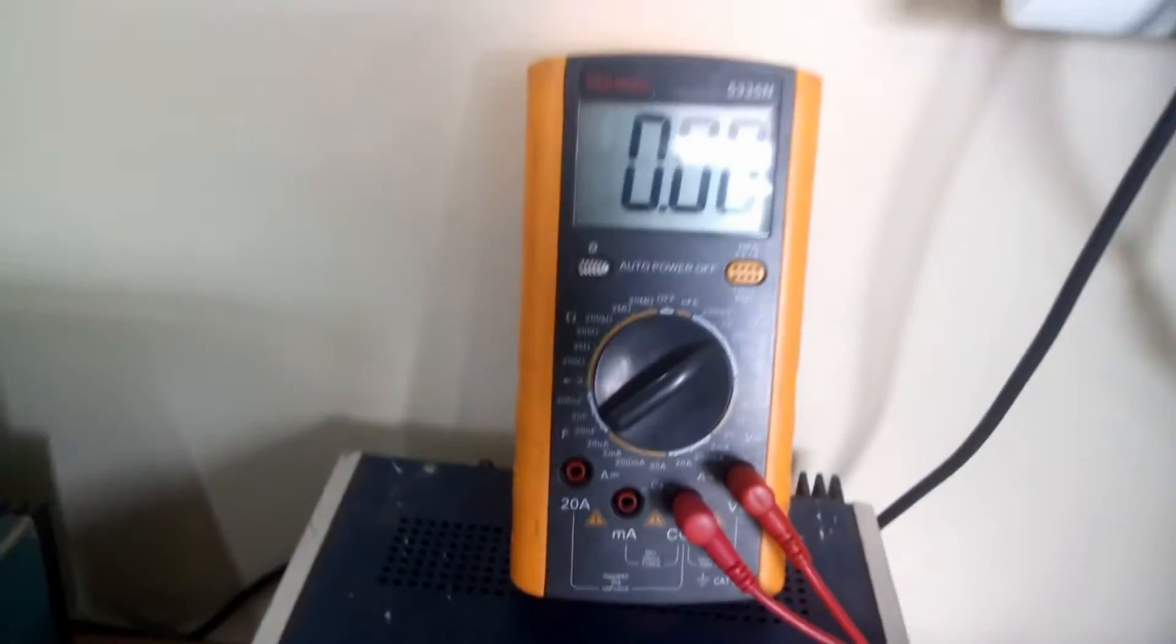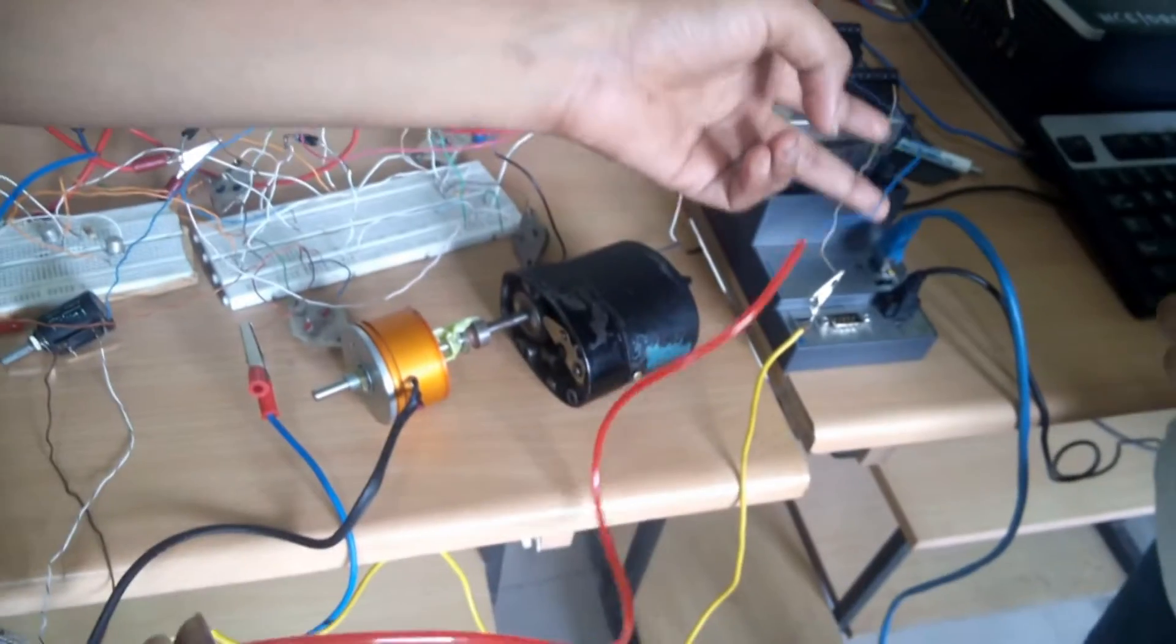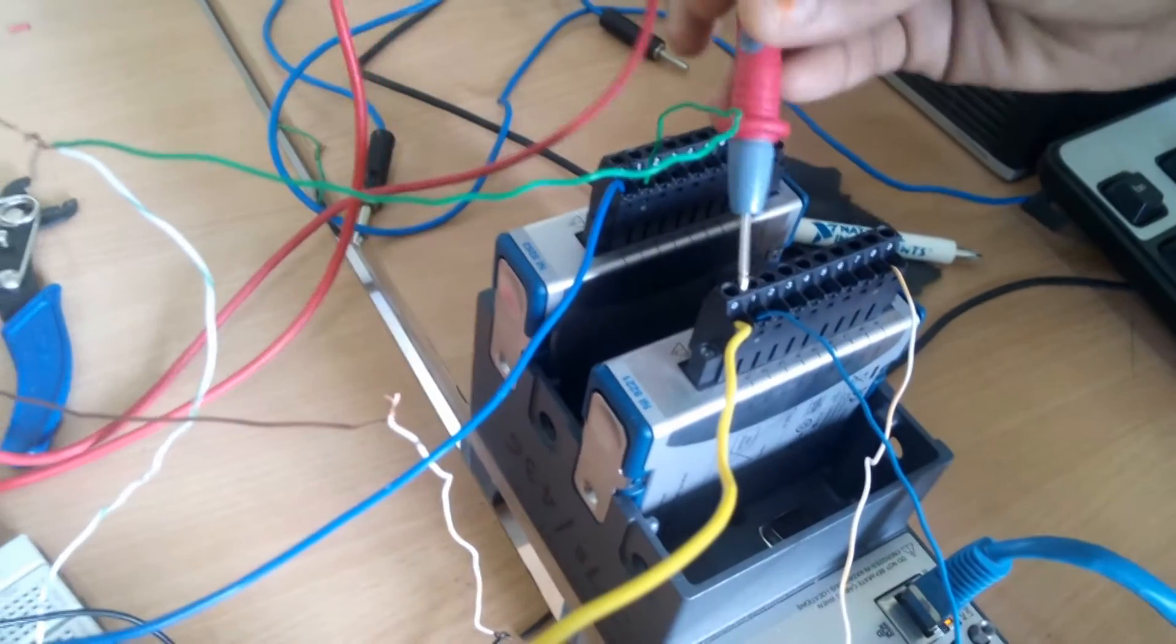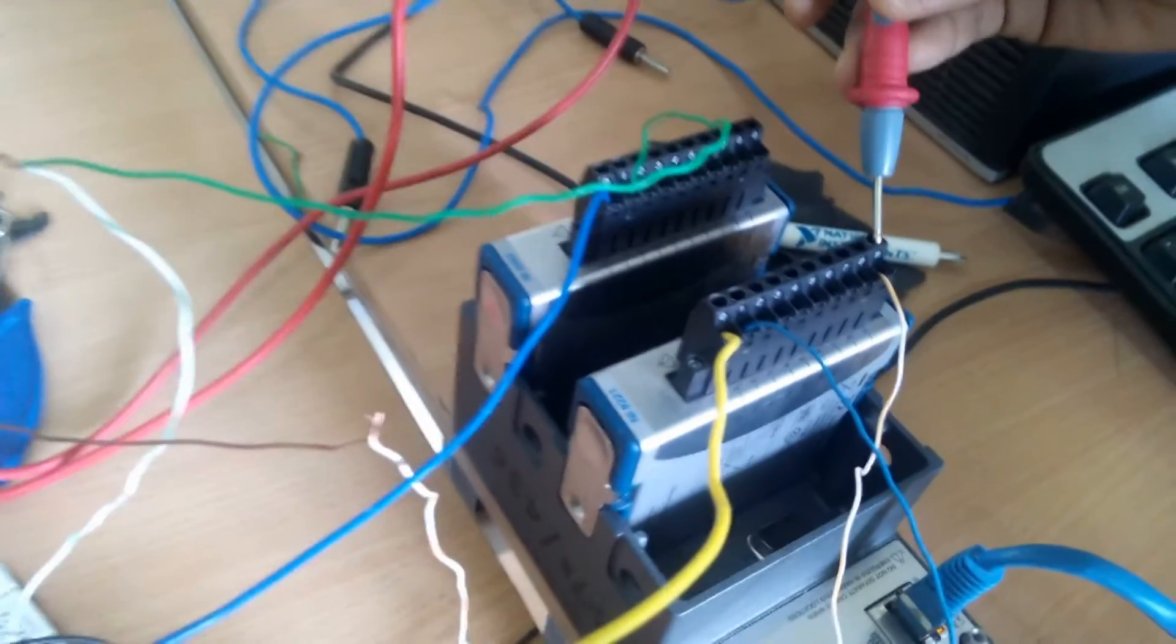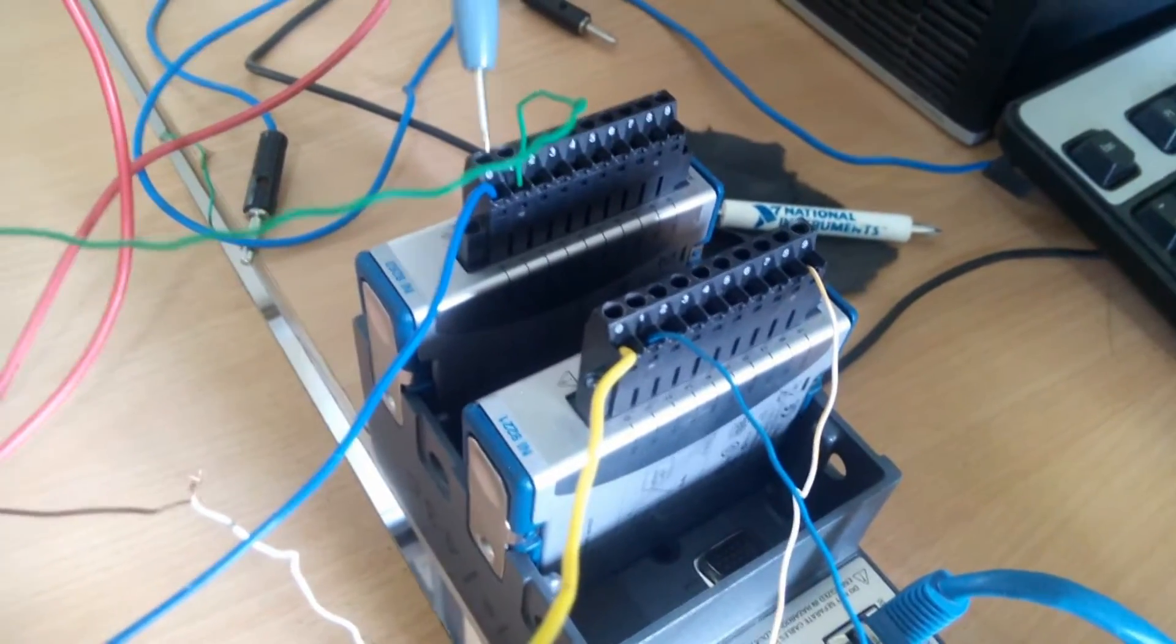We can see the multimeter. This is this one the yellow wire. Yellow wire is the set point. And this blue wire is the process variable. And here it is the analog input. The first two, these are both, 8 are our input. And the ninth one is our ground. In analog output module, the first one is output. And the next to first is our ground. It is the architecture in build. So we will see our values of voltages.